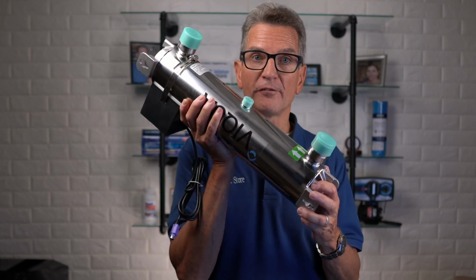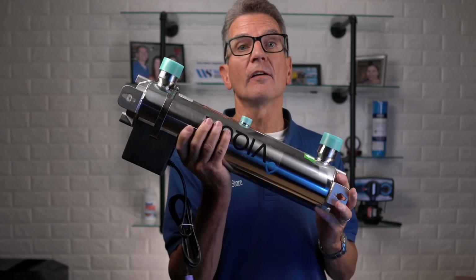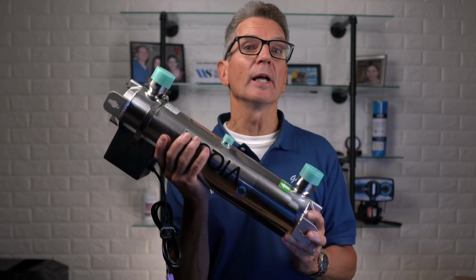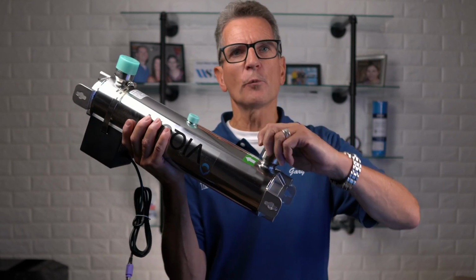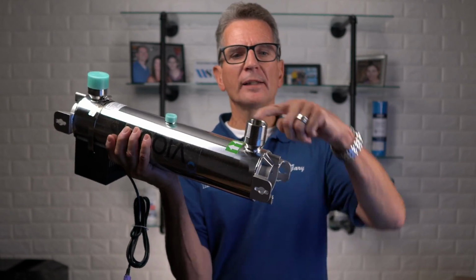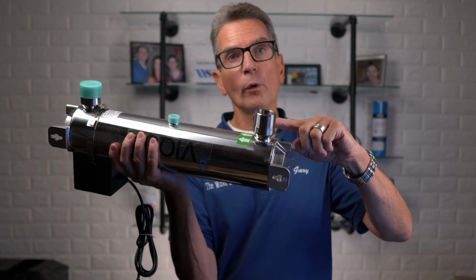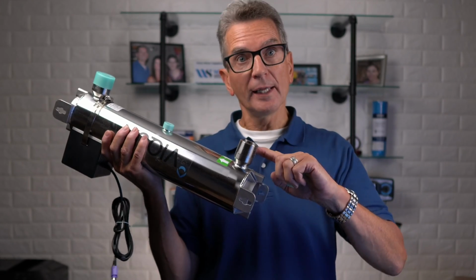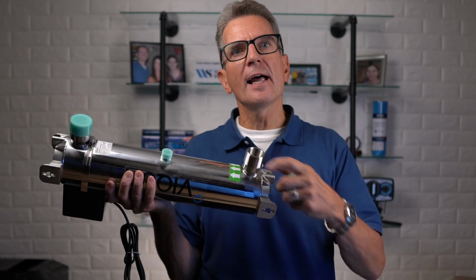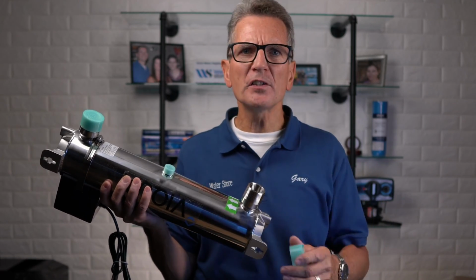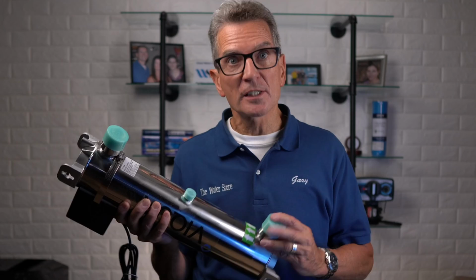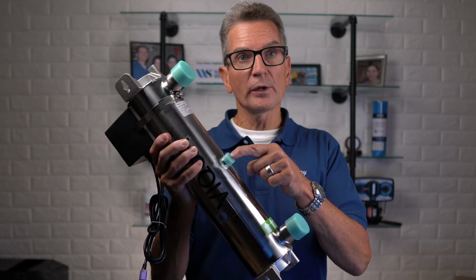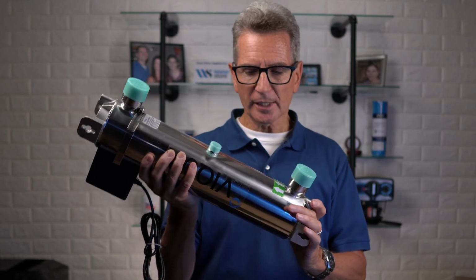So this is the activation chamber by itself. And as you can see, it's a very strong, very heavy, well-built stainless steel unit, but it has some really cool features. So one of them that I really like is that it's a 1¼-inch male thread on the outside, but on the inside, it has a 1-inch female thread. So it gives you some flexibility with installing. And this is where the sensor goes to check the UVT.